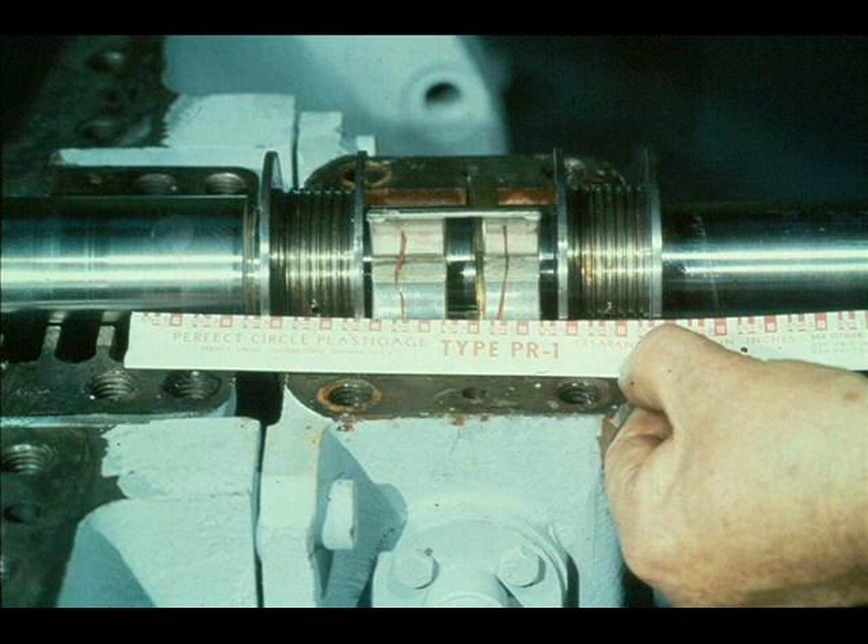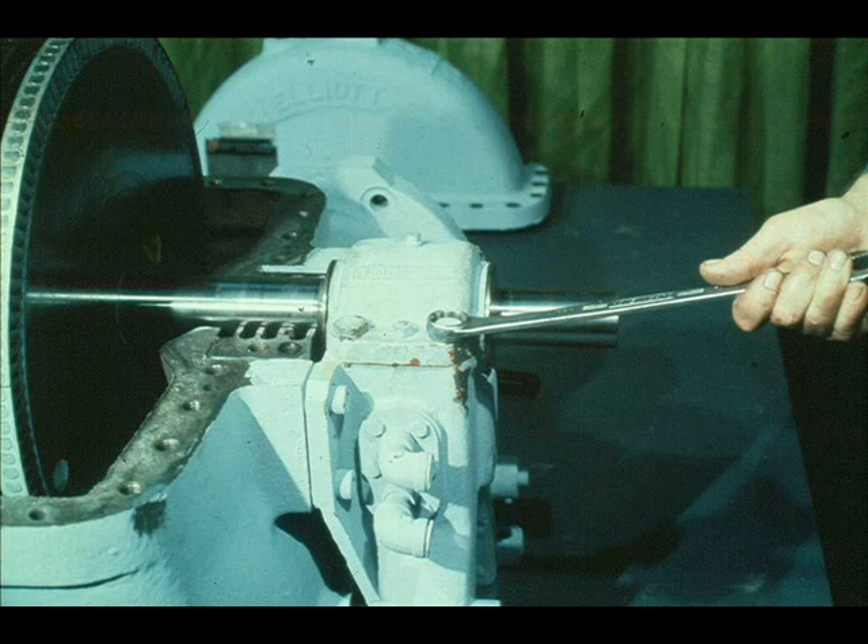Using the Plastigage scale, the workman measures the width of the Plastigage and determines the actual clearance between the bearing liner and the shaft bearing journal. He checks the figures against the manufacturer's specifications. If they are satisfactory, he removes the Plastigage. The workman then replaces the bearing liner and cap and tightens the cap screws securely.